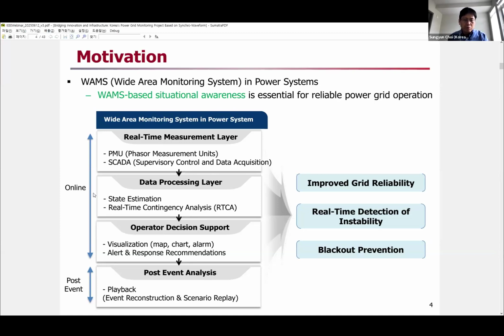Based on these measurements, the data processing layer performs state estimation and real-time contingency analysis. It's kind of an analysis of the system. State estimation provides the phase angle based on the measurements and the system model. With the introduction of PMU, the accuracy of state estimation becomes higher because the PMU itself can measure the phase angle in some places. But not all places can be covered by PMU. In some places, it is mostly covered by SCADA. So state estimation is still required. And then based on that, the operator makes decisions, for some kind of visualization or actions that are required.